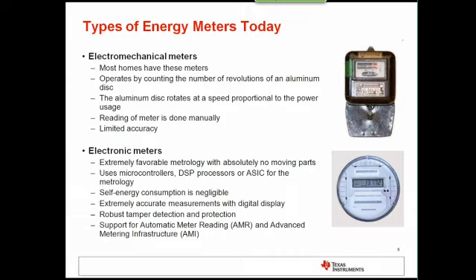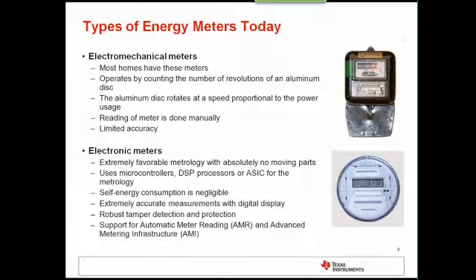The second type of meter is electronic meters. It's extremely favorable for metrology, with absolutely no moving parts. You have current and voltage sensors and microcontrollers or DSP processors to use those sensors to calculate the power as necessary. One advantage of this type of meter is that self-energy consumption is negligible, which puts less strain on the electrical grid. It also has a digital display, which provides more accurate measurements compared to electromechanical meters. Another feature is that with electronic meters, you can determine when a meter has been tampered with and take necessary action. Also, electronic meters support automatic meter reading, which is one-way communication from the meter to the outside world, and advanced meter infrastructure, which is two-way communication from the meter to the outside world.